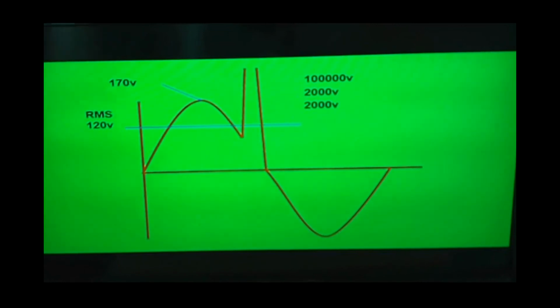Now, categories on meters have been around since 1987. This is when they first started acknowledging the transient threat and the transient hazards. So meters have been identified with categories. If you find a meter that is not marked with a category at the test leads, then that meter was manufactured before 1987, and it is considered a Category 1 meter. So a lot of the old meters that people like to use, especially the old analog Simpsons, are actually only rated today as Category 1. So meter categories, guys, this is a safety rating.